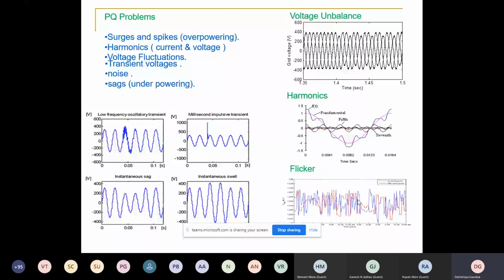You can see more of this especially on an incandescent light, where you can easily observe this kind of variation effect. The power electronics, the wind turbines and other things are creating this issue, so you should be able to control it. Harmonics is another important thing. As per the IEEE standard, you should be able to maintain the harmonics within plus or minus 5%. In isolated operation it may be plus or minus 8 to 10%. But imagine 10 generators with power electronics injecting a lot of harmonics at the grid level; the harmonics level may go up. So reduce the harmonics level.